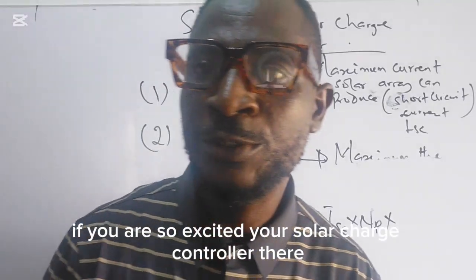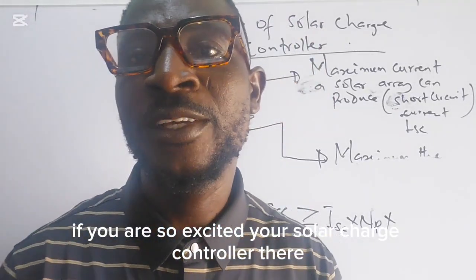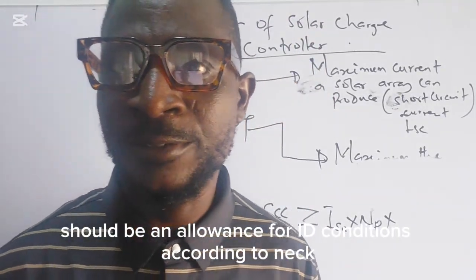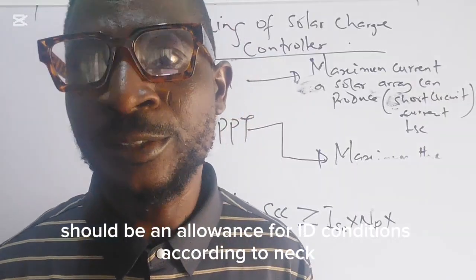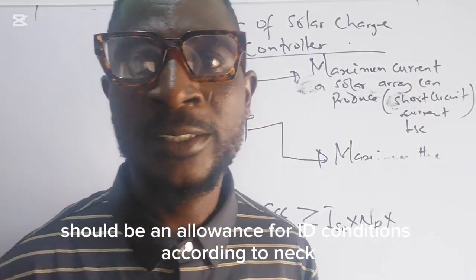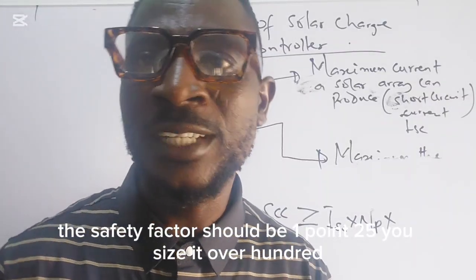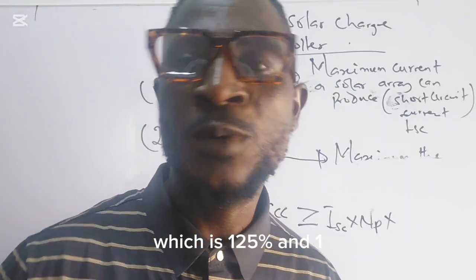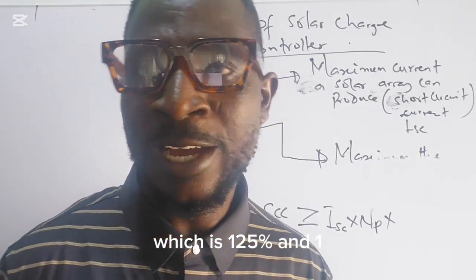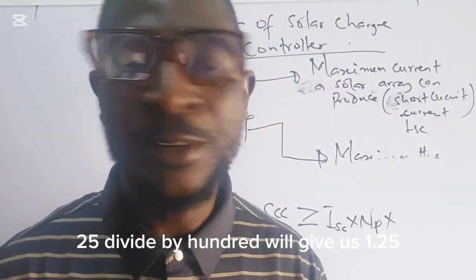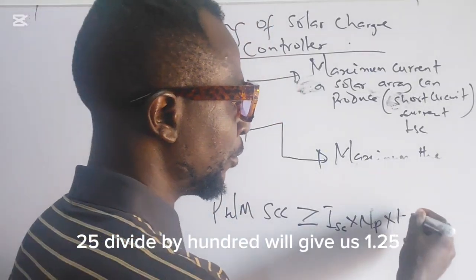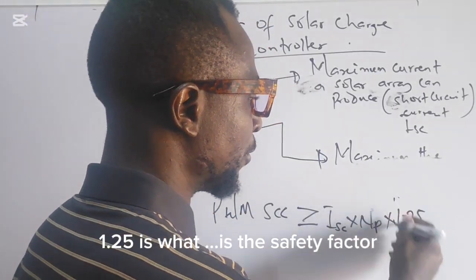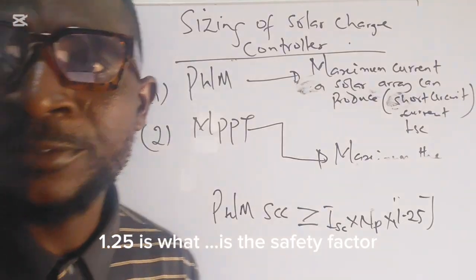What is this? If you are sizing your solar charge controller, there should be an allowance for ideal conditions. According to NEC, the safety factor should be 125%. You size it over 100, which is 125%, and 125 divided by 100 gives us 1.25. 1.25 is the safety factor.